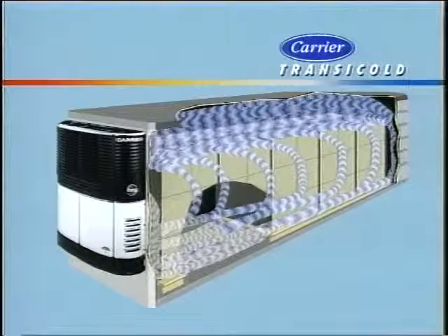Manual defrost key will initiate a defrost cycle once the box temperature is below 40 degrees. Pressing the manual defrost key once will put the unit into the defrost cycle. The unit also comes with an automatic defrost switch and defrost timer. If the box temperature is too warm for the unit to go into defrost, the message center will show cannot start defrost cycle.